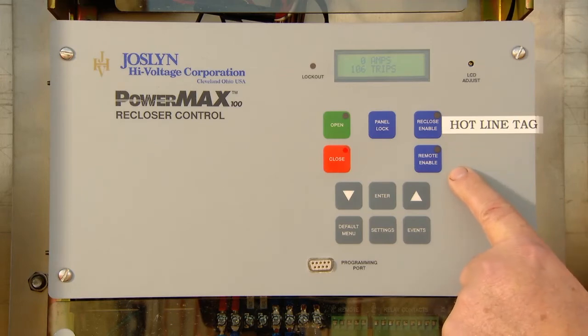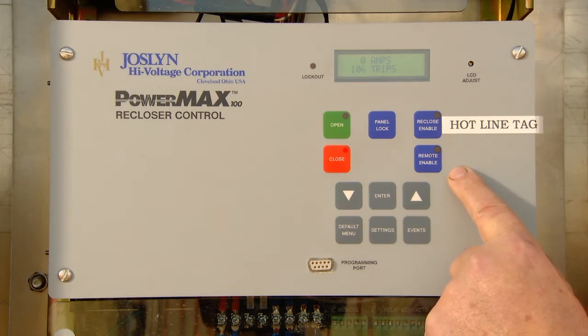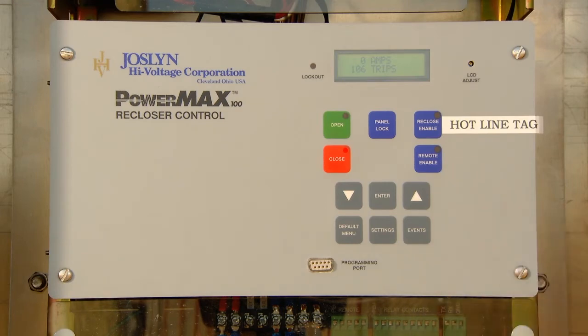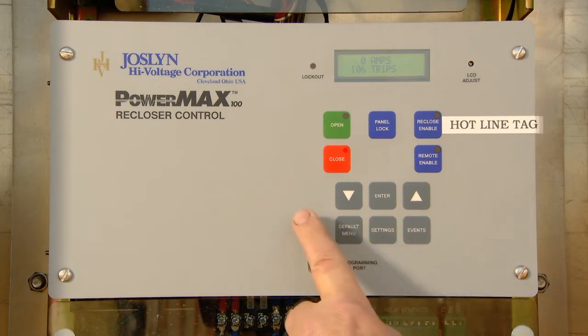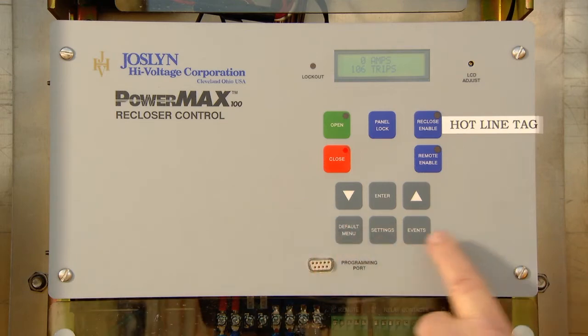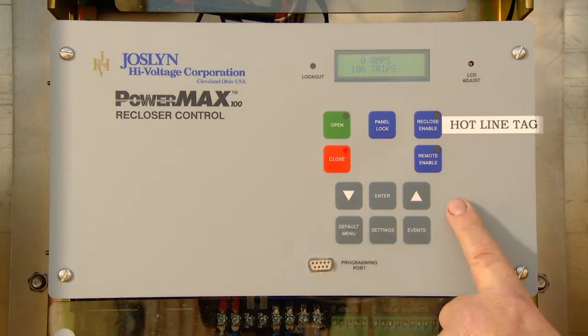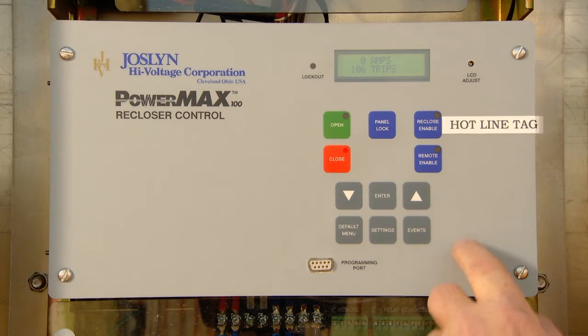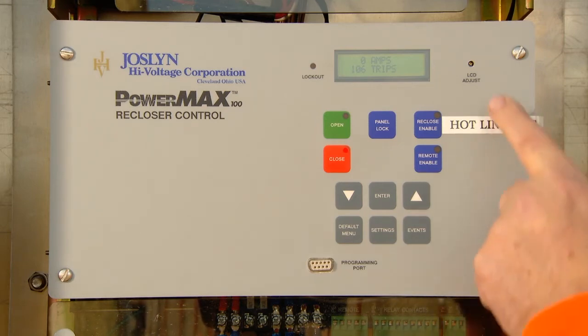Below that is the Remote Enable, which is typically not used because it's for SCADA communications or remote applications, where this unit would be controlled by a remote operator. Next, we have the default menu button, a settings button, an events button, as well as a scroll arrow up and a scroll arrow down. These will allow you to scroll through the different applications, which will be displayed on the screen.